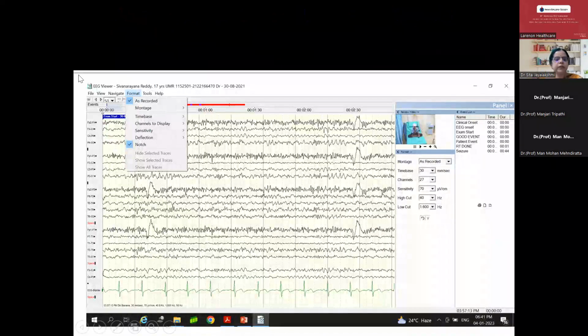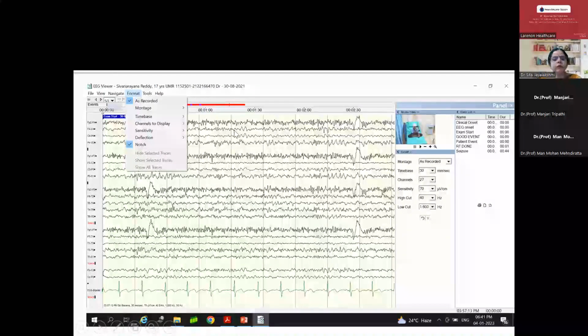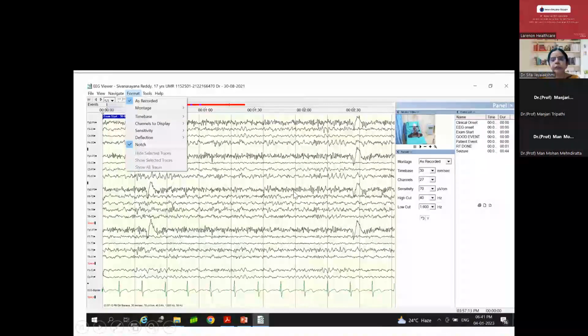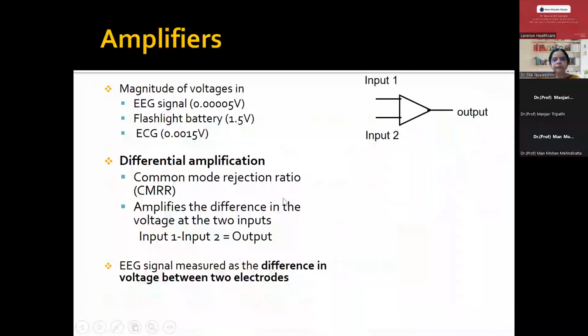The next important thing is when you look at an EEG, when you are recording, you look at the channels to display, the time base, the montage, the sensitivity of the machine, and also there is something called the notch filter. So why do you need to have all this? There is a high cut filter and again a low cut filter. So we'll come to the details of this.